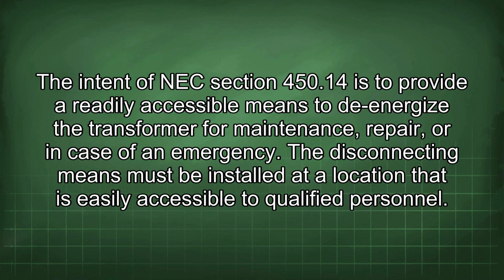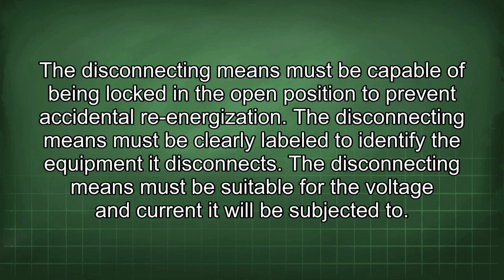The intent of NEC Section 450.14 is to provide a readily accessible means to de-energize the transformer for maintenance, repair, or in case of an emergency. The disconnecting means must be installed at a location that is easily accessible to qualified personnel. The disconnecting means must be capable of being locked in the open position to prevent accidental re-energization.